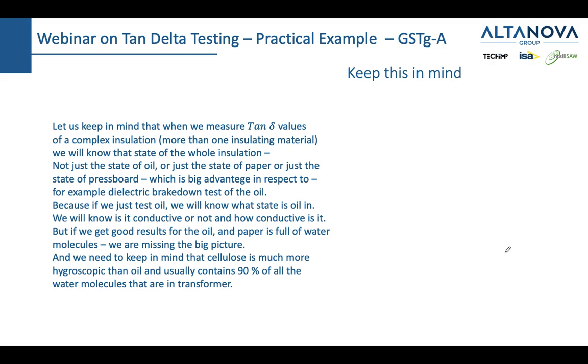So what I would like to mention here, and allow me to read this, let us keep in mind that when we measure tan delta values of a complex insulation, so oil, press board, paper, we will know the state of the whole insulation, not just one segment. So we will not just know the state of the oil, or just the state of the paper, or just the state of the press board, which is a big advantage with respect to, for example, the dielectric breakdown test of the oil, which also has its place. But you can have a perfect oil, and since most of the water molecules are in the cellulose, in the paper and press board, it doesn't help you if you have fully functioning oil and damaged insulation in the cellulose. So what I'm trying to say here is that tan delta gives you a bigger picture, not just a picture of one segment.